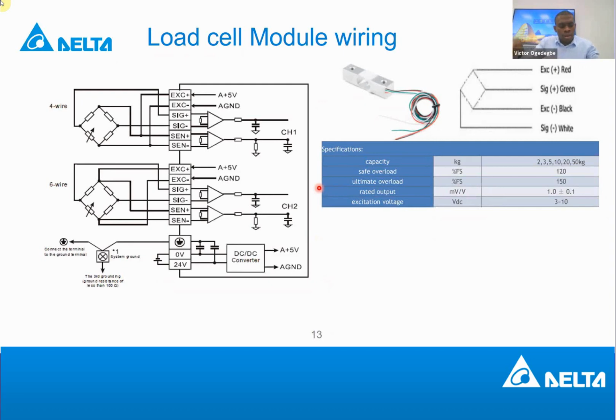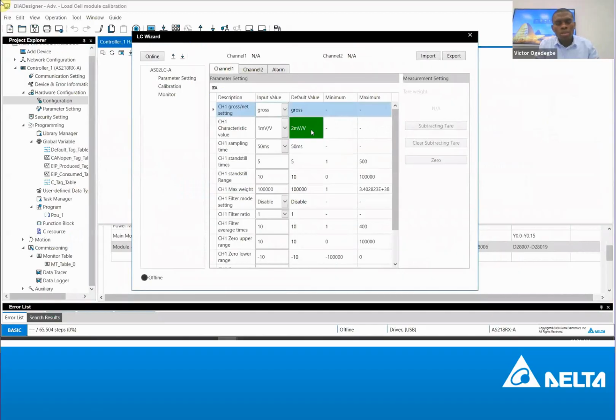So if I go back, you can see where we opened the load cell module, the load cell wizard. So now here we select the gain value. The maximum we support is 80. So it means that for this sensor, the gain value supported is 1 millivolt. So if you want to have a correct reading, you must select 1 millivolt. If you select something else, the reading will not be accurate. So this is very, very important.